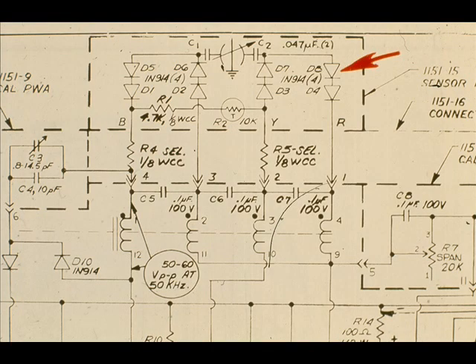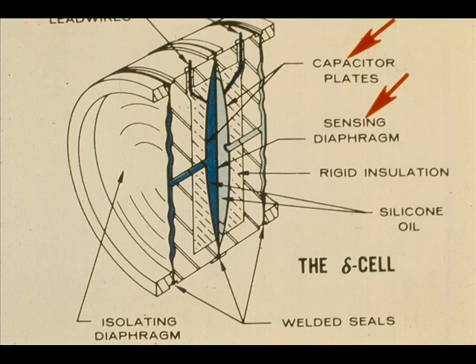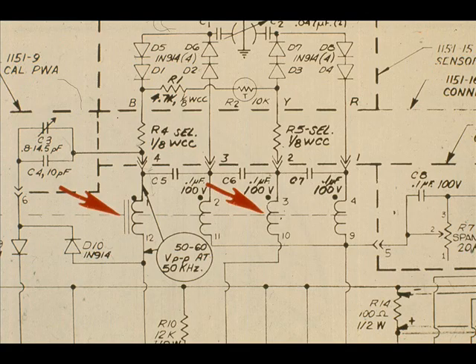The variable 50 kHz signal is demodulated by an eight-diode bridge rectifier — the diodes are D1 through D8 on the schematic. The output currents from the rectifier are related to the difference in capacitance between the sensor and the plates. Two of the output currents are algebraically summed, and the net current is directly proportional to the differential pressure.